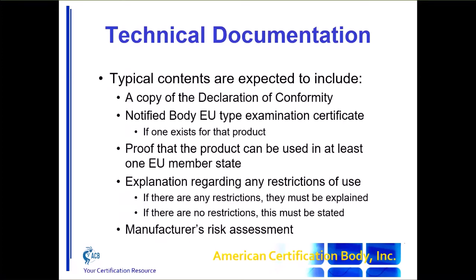A copy of your declaration of conformity. A copy of your notified body certificate, if indeed you have one. Proof that your product can be used in at least one EU member state. And if it is a class two device with restrictions, then that would be listed in your technical documentation and your manufacturer's risk assessment.